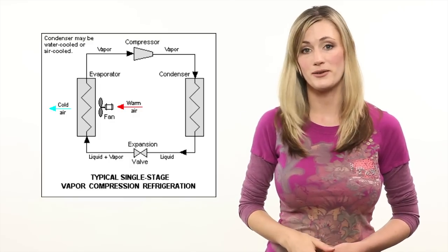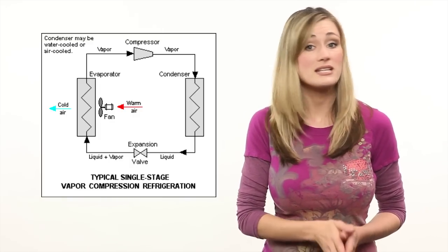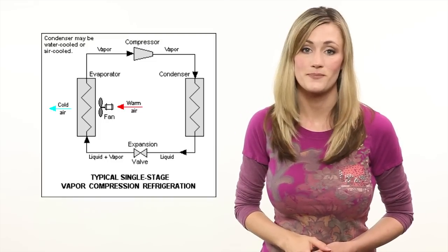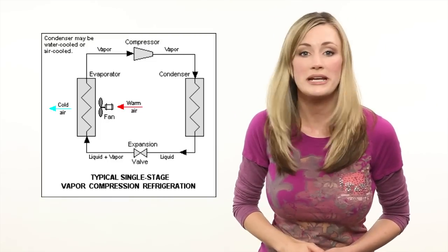Most air conditioning systems work by a process engineers call a vapor compression refrigeration cycle. A fluid with unique thermodynamic properties called a refrigerant is forced through a powered compressor as a gas. The refrigerant exits the compressor as a high-pressure superheated gas.